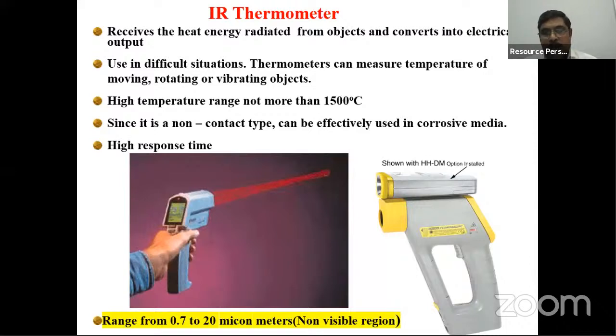This is an important parameter. Each instrument is designed for a certain focal length, so you have to use the instrument within that focal length. If you go nearer to the target or away from the target, then you will have a problem.